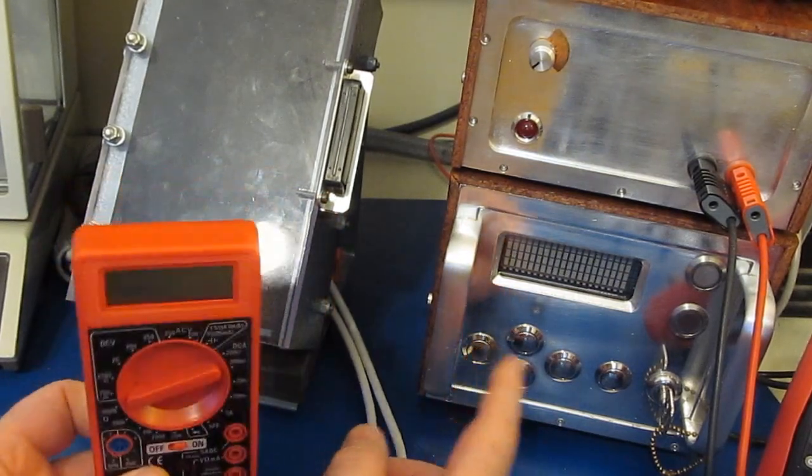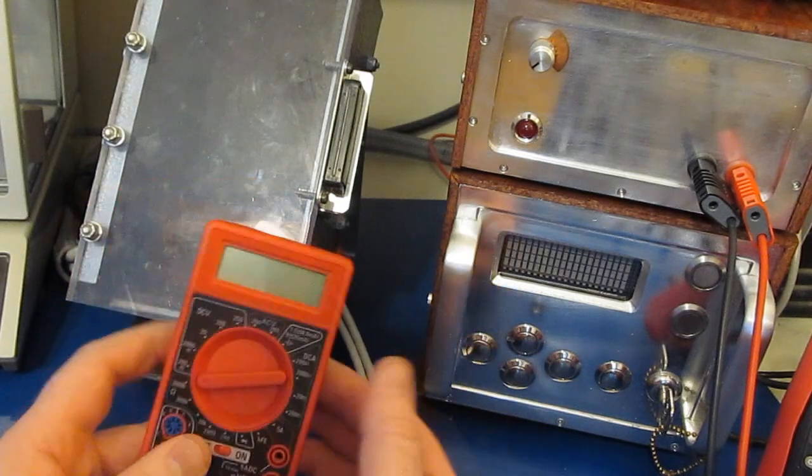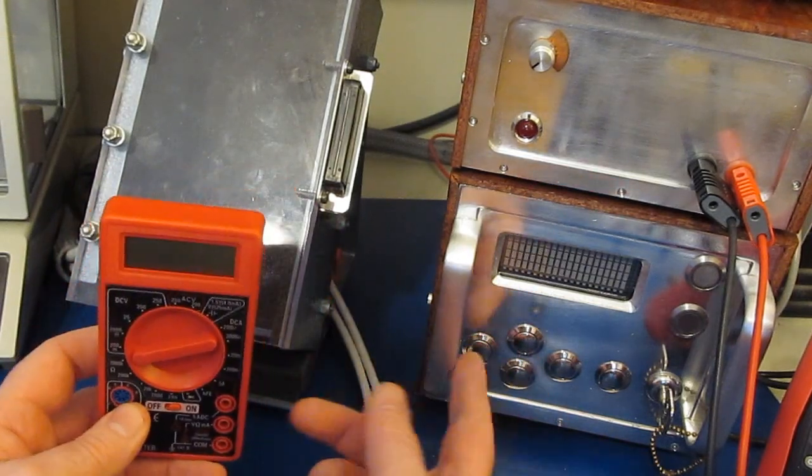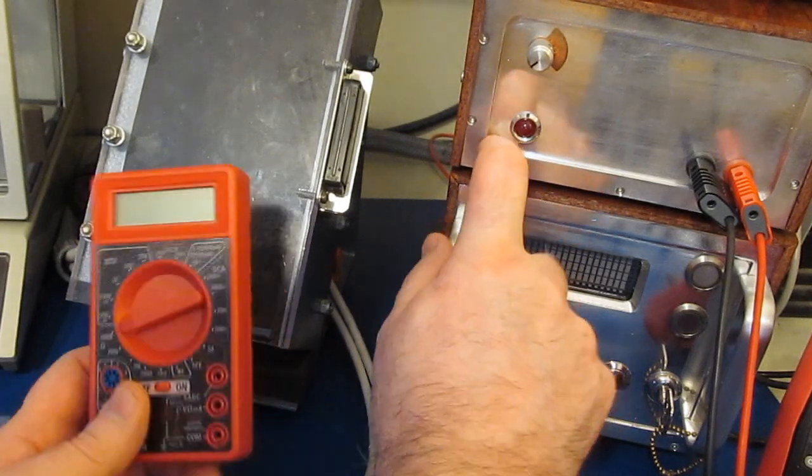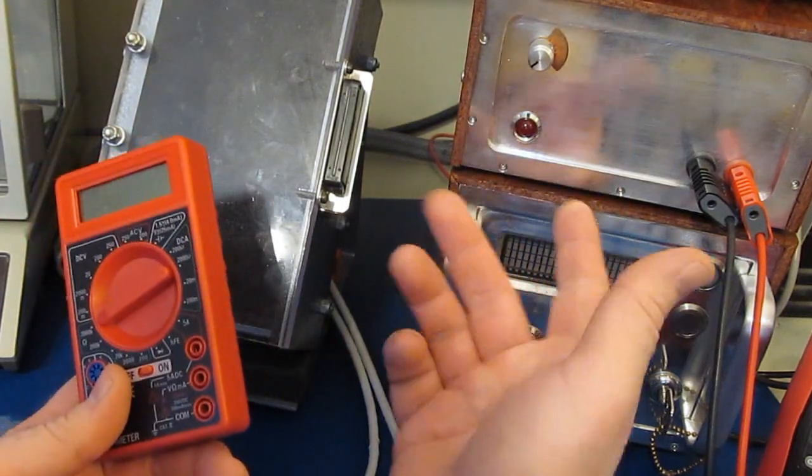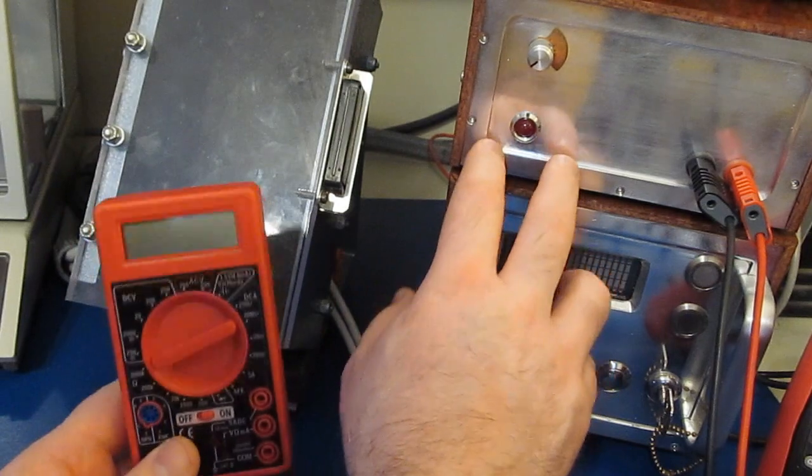So what ends up happening is if the meter breaks down and we get an arc, so we get this low impedance path, that will trigger up this generator here which will feed that low impedance path. That's why we don't need a high voltage. Anyway, that will feed into that arc and we can get a fair amount of damage.